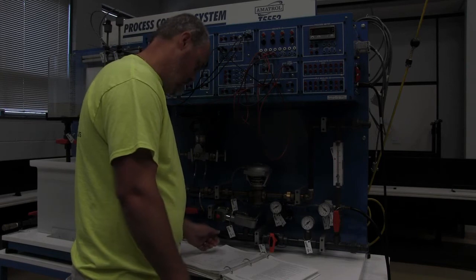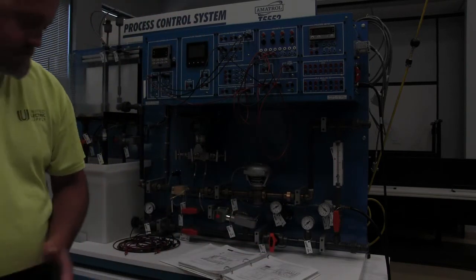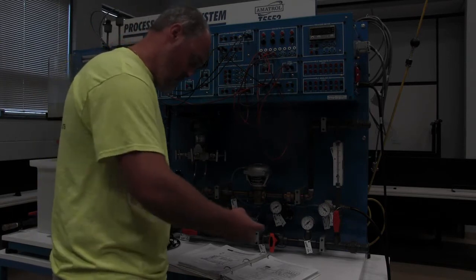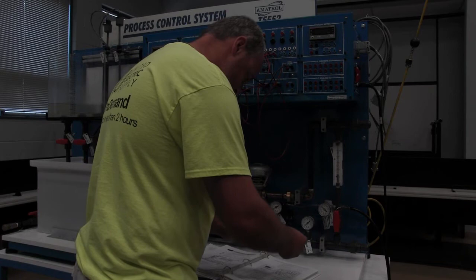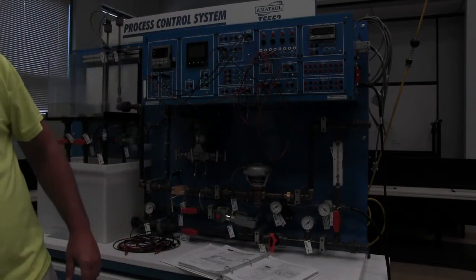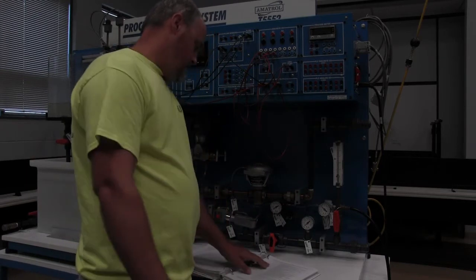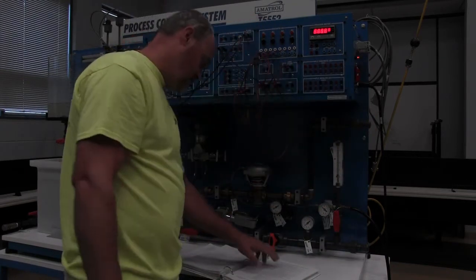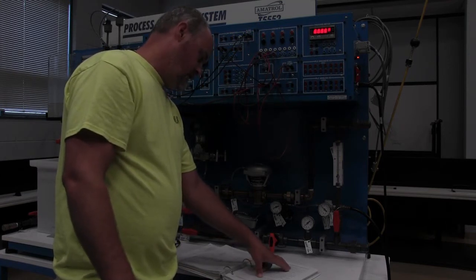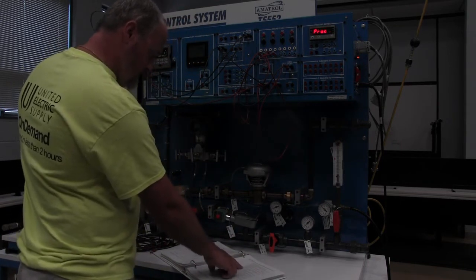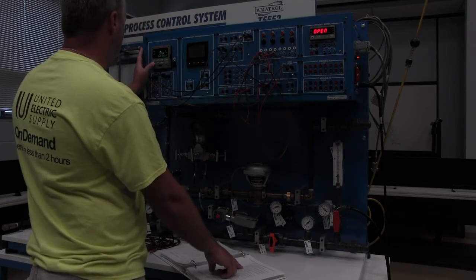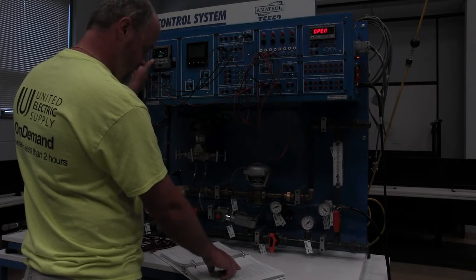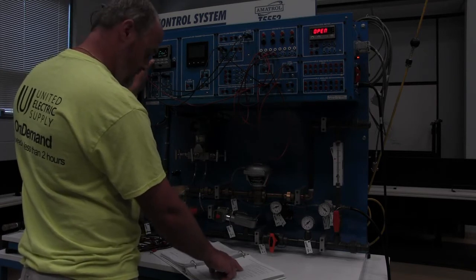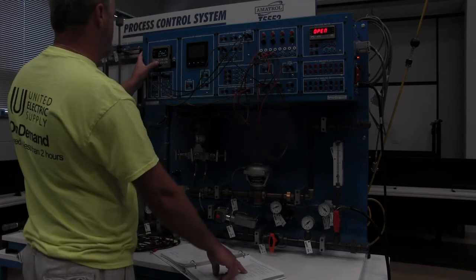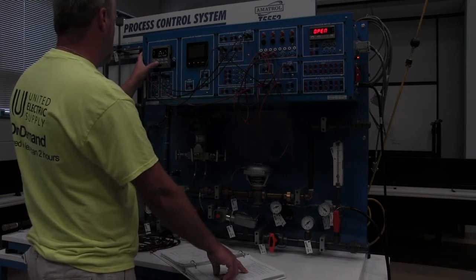Now that we've got that wired up, alright, so now we're going to turn it on. Make sure these are both in the off position. Perform the following sub-steps to set up the Honeywell controller. Once the test is done, we're going to press the setup key till we see input 1. Input 1. Press the function loop key till we see in type. And then we're going to use the up and down to go to 1 to 5 volts.